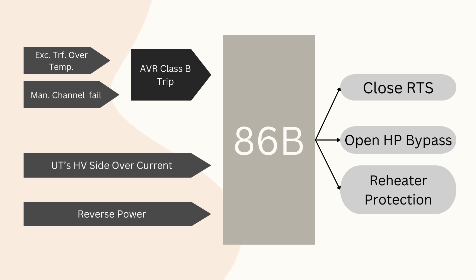In the Class B protection scheme, some electrical protections are also provided where instantaneous tripping is not required. Protections of the turbine go with 86B, and some excitation system protections — like excitation transformer over-temperature and manual channel fail — will not cause any instantaneous damage to the system. Along with these, UT HV side over-current protection and one contact of the reverse power relay are also provided.